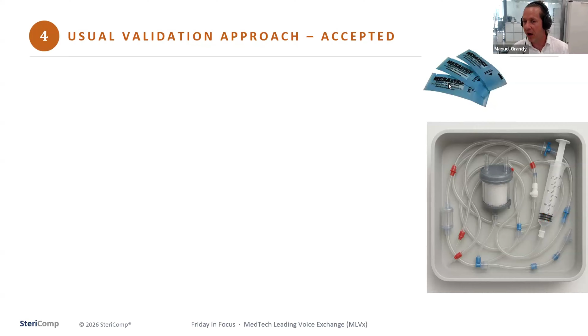So where to put these BIs? You would put them at parts where you want to show that EO, or also steam, and lethal conditions are reached, because this is your indicator that is showing you I killed 1 million spores. So if you put it somewhere, it will be, of course, easier for EO to kill a spore on the surface of this tray, as opposed to here in this lumen. So this is a very usual place to put a BI.